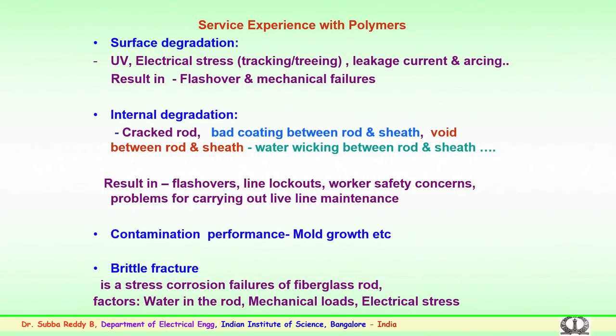Similarly, electrical stress: because the insulators are continuously under electrical stress, they are prone to tracking and treeing. If the surface becomes hard, stiff and brittle over a period of time, the hydrophobicity property which we were discussing could be reduced because of the continuous hardening of the silicone rubber. This leads to higher leakage currents leading to arcing.